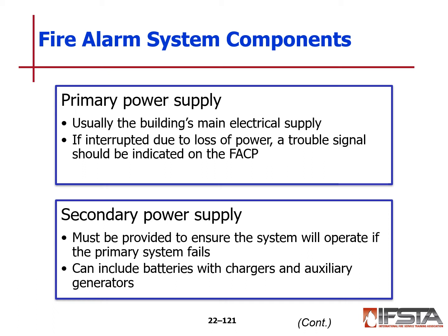Primary power supply to these systems usually is the building's main electrical supply. If it gets interrupted due to loss of power, a trouble signal usually is indicated at the panel, and there is a battery backup for that panel. This is another area in these types of systems where we'll see that the batteries do not function properly, and so they simply need to be replaced.